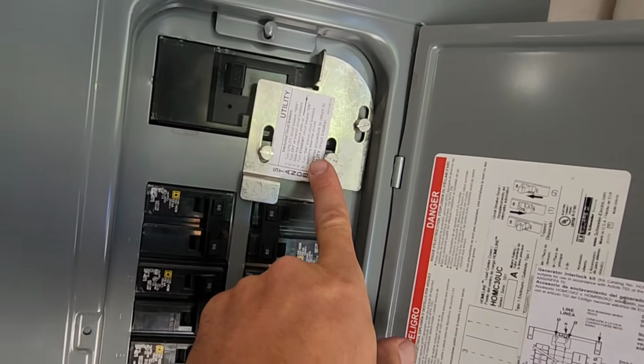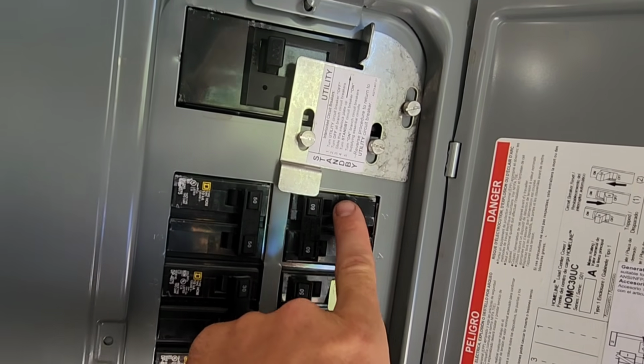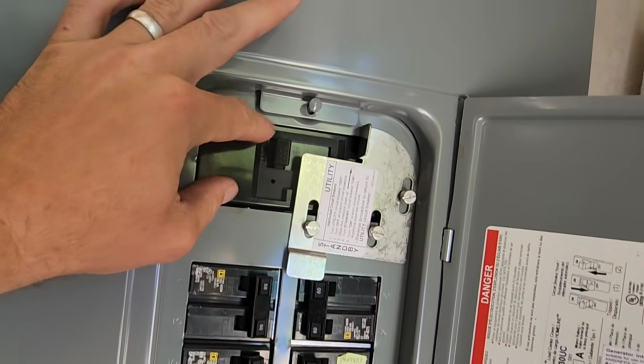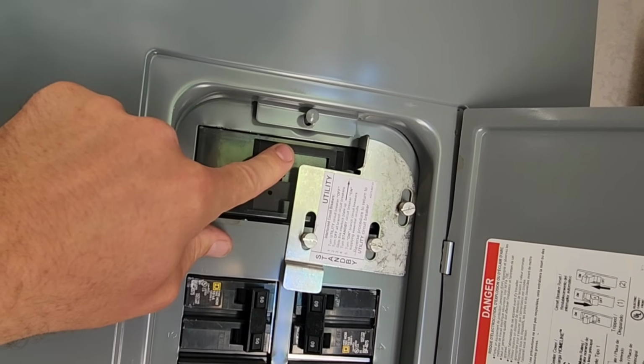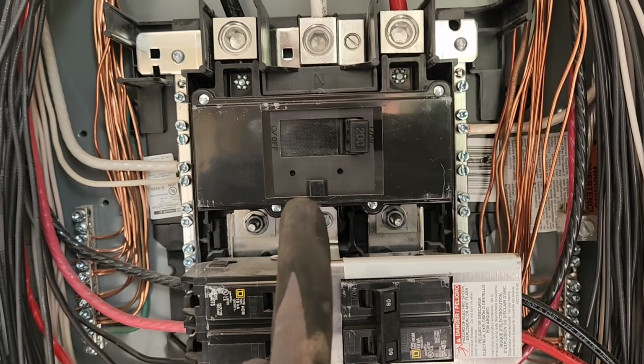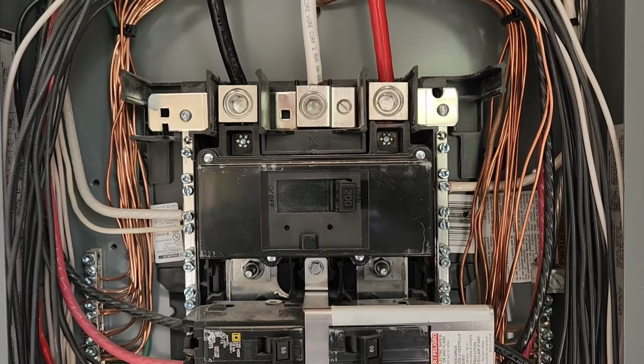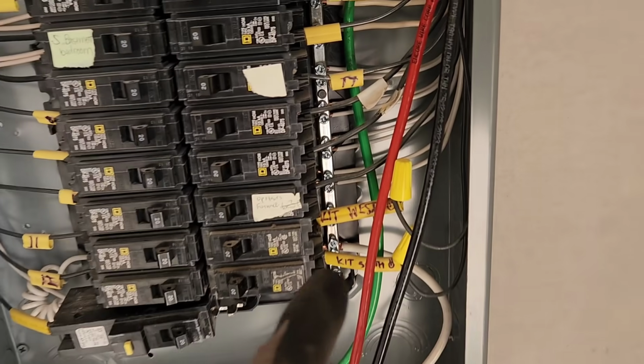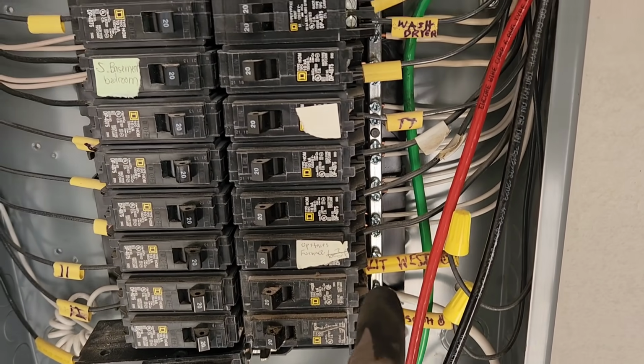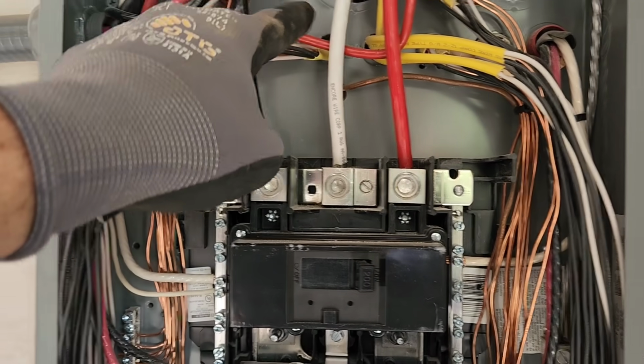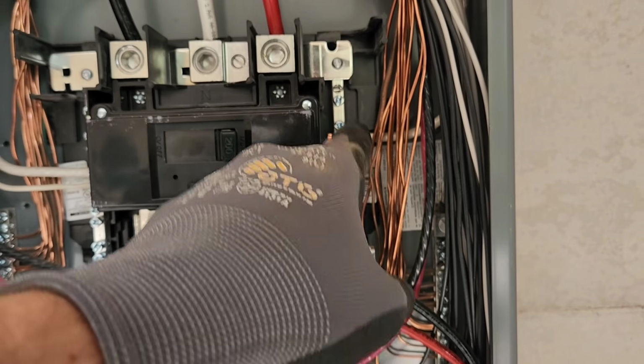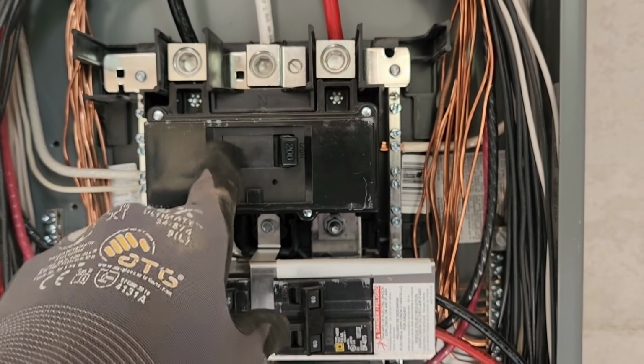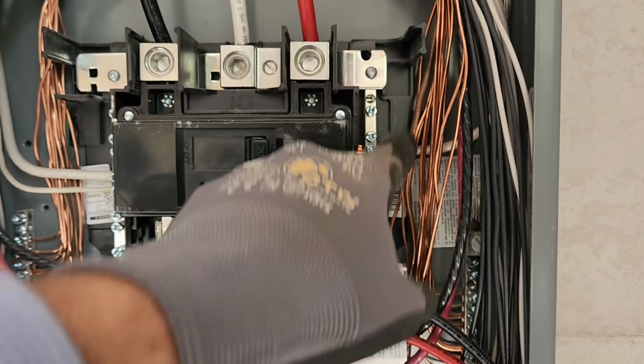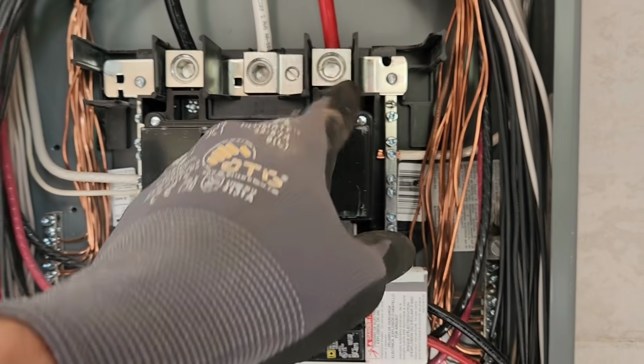I've got a little interlock kit, so when this is on, it forces this to be off, so I'm not back feeding into the main electrical panel. I've got my neutral that comes through here, and I could have a neutral connected here as well, but this neutral bar is connected to this regardless, so there's always continuity between the neutrals.